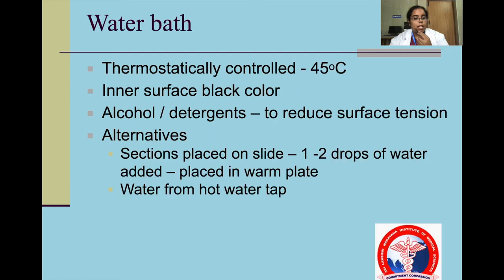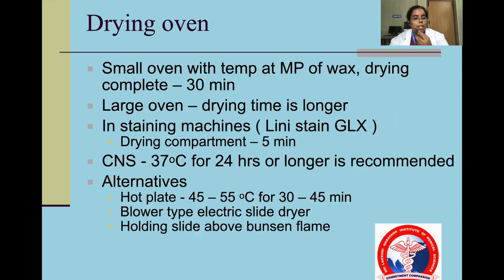The water bath is a thermostatically controlled water heater that maintains water at 45 degrees Celsius. Alternatives include placing 1 to 2 drops of water on a warm plate or using water from a hot water tap. The dry oven is used to maintain the temperature at the melting point of wax, drying completely for 30 minutes. Alternatives are hot plates, blower type electric slide dryers, and holding the slide above a Bunsen flame.